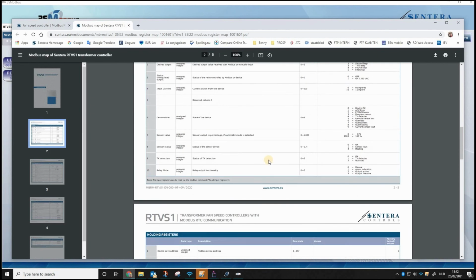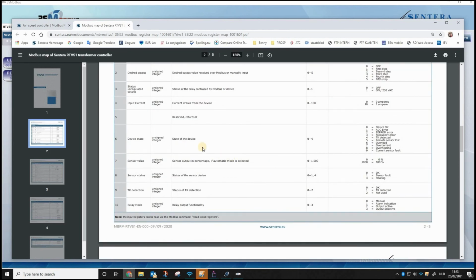And if we return for a moment to the issue of the alarm status that we just discussed, you will see that the value 0 indicates that the device is operational, but that there are 9 different reasons why an alarm can occur. For example, if a TK, thermal motor issue, is detected, or if there is an overload from the motor, or overcurrent, or overheating of the unit itself, and so on.